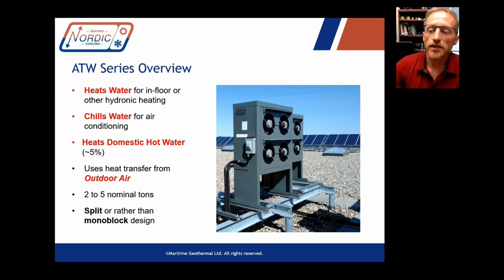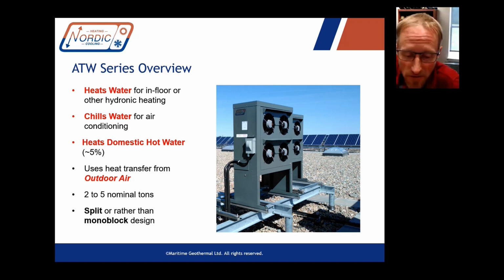the desuperheater does what it can. Yeah, it might heat the water all the way up, but it might only get it to a lower temperature than what you require for the house. So then a final heating device will take water from that preheat tank and heat it the rest of the way if needed. Okay, but it's an electric tank. Yeah. Right. Another tank. Yeah. Okay. So you have a 40-gallon, but especially if you're in a multi-family setting or whatever, you probably need to bring that into another 60-gallon or whatever kind of final water heater they would have anyway. So it could be an instantaneous heater, even the final heater. But for a preheat tank, I would normally just choose a 40-gallon electric water heater without the elements hooked up.